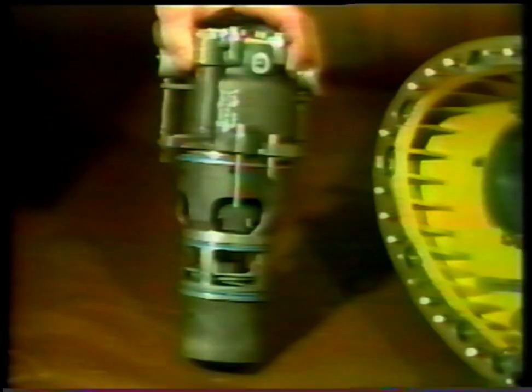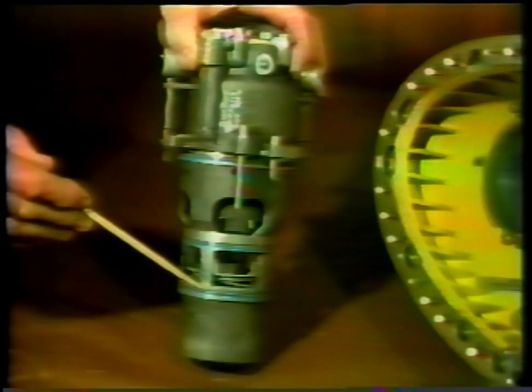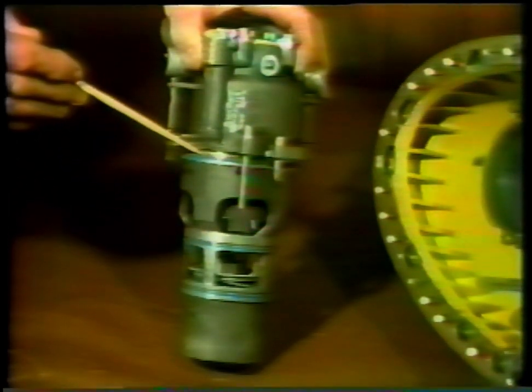As each screw is removed, make sure that it is free of the threads and loose in the hole. Be sure the ground strap screw is clear before trying to remove the pump. Lifting the handle breaks the pump loose. Then pull straight out on the pump without twisting it until it stops. Then turn the pump body counterclockwise about 12 degrees and remove it. The pump body has 3 different O-rings on it and may require as much as 150 pounds of force to break it loose.